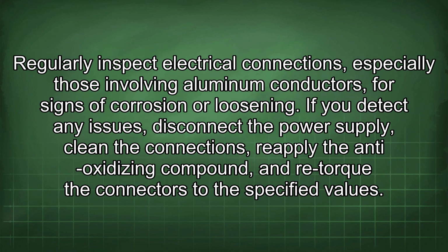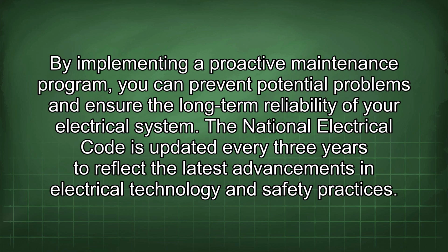Regularly inspect electrical connections, especially those involving aluminum conductors, for signs of corrosion or loosening. If you detect any issues, disconnect the power supply, clean the connections, reapply the anti-oxidizing compound, and retorque the connectors to the specified values. By implementing a proactive maintenance program, you can prevent potential problems and ensure the long-term reliability of your electrical system.